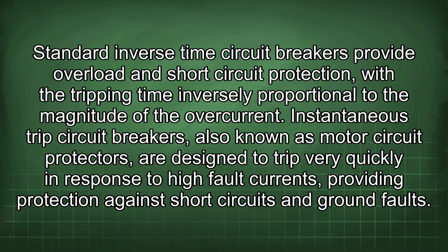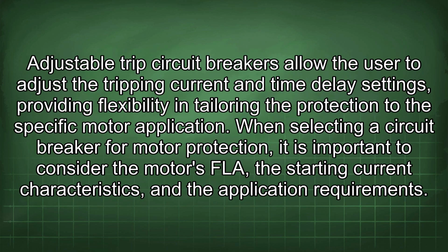of the overcurrent. Instantaneous trip circuit breakers, also known as motor circuit protectors, are designed to trip very quickly in response to high fault currents, providing protection against short circuits and ground faults. Adjustable trip circuit breakers allow the user to adjust the tripping current and time delay settings, providing flexibility in tailoring the protection to the specific motor application.